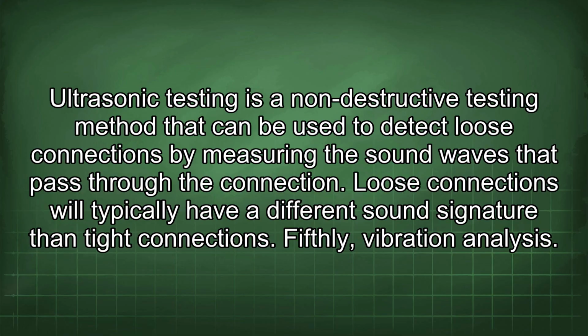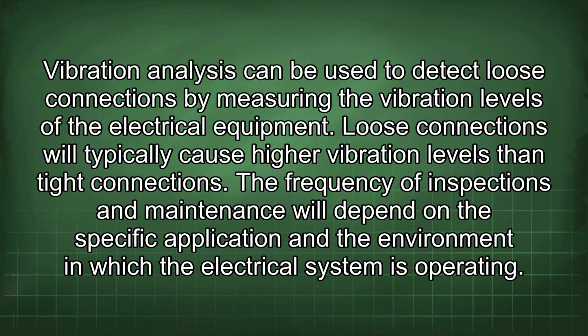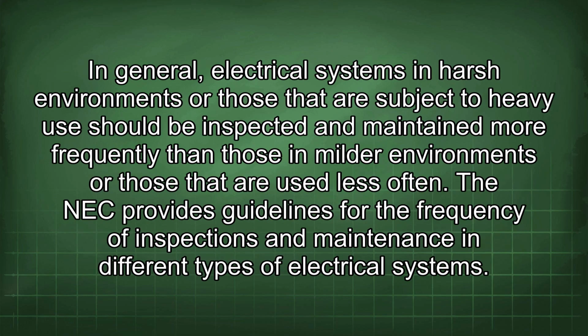Fifthly, vibration analysis. Vibration analysis can be used to detect loose connections by measuring the vibration levels of the electrical equipment. Loose connections will typically cause higher vibration levels than tight connections. The frequency of inspections and maintenance will depend on the specific application and the environment in which the electrical system is operating. In general, electrical systems in harsh environments or those that are subject to heavy use should be inspected and maintained more frequently than those in milder environments or those that are used less often.